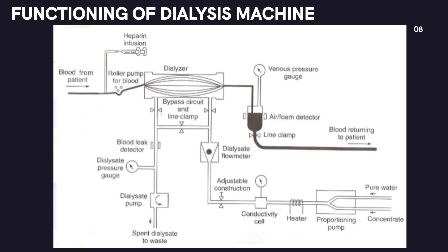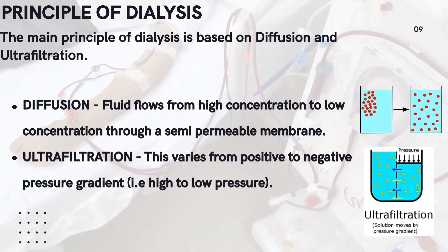After completing the purification process, the used dialysate enters a waste collecting tank while purified blood passes through the patient's body. The machine also contains sensors, an air detector, and alarms. Sensors monitor various parameters such as blood pressure, dialyzer pressure gradient, temperature, and oxygen saturation. The air detector near the venous pressure line detects any air leakage or air molecules in the blood entering the patient's body. Alarms are used to detect and prevent errors in blood flow, blood pressure, temperature, and dialysate mixture.